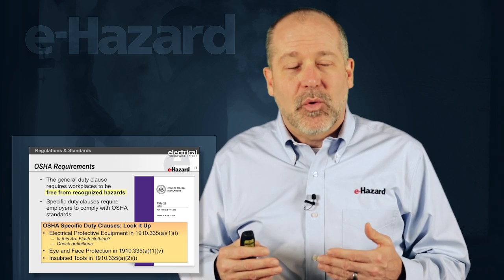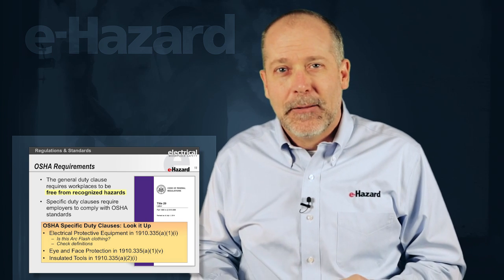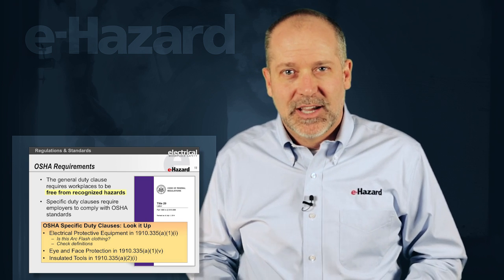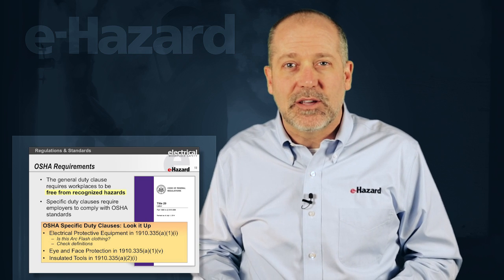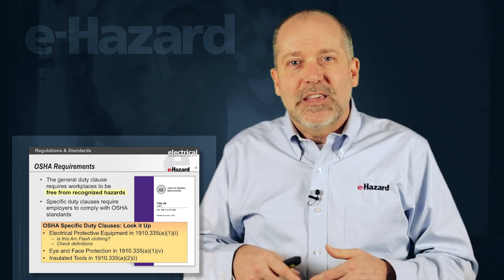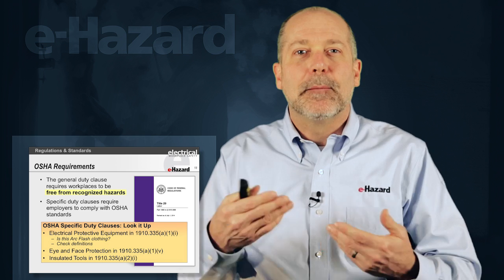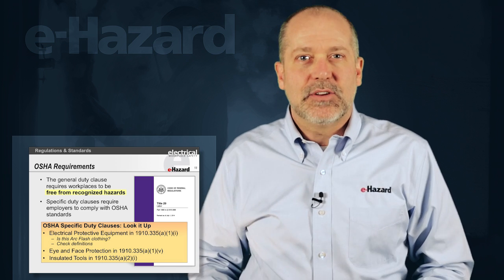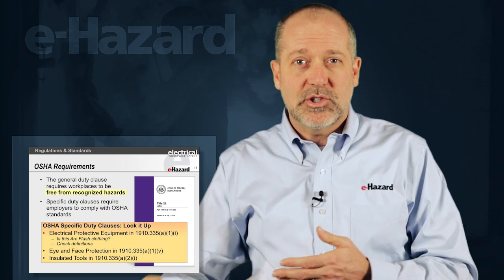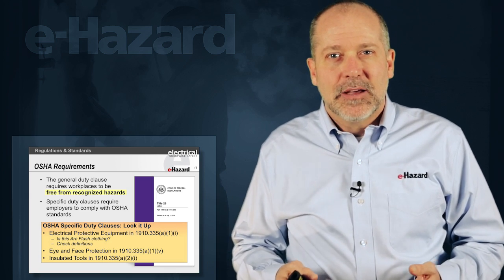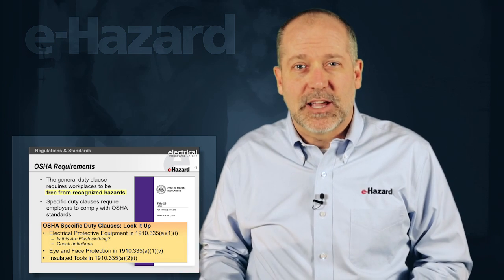Eye protection was required to be a face shield and/or eye protection like safety glasses since 1991 to protect from arc flash. Yet in 1991 there were no arc flash rated shields; that didn't happen until about 2002. So these standards changed. The OSHA standard may be the same, an underlying performance-based standard, but how you comply with it may change over time. 70E got very prescriptive: when you're exposed to this, you wear a shield; when exposed to this, you wear a hard hat and a shield; when exposed to this, you wear a hood. So there are lots of things that change over time. The OSHA standard, being very general, may remain the same, so how you comply with this particular section is something to think about.